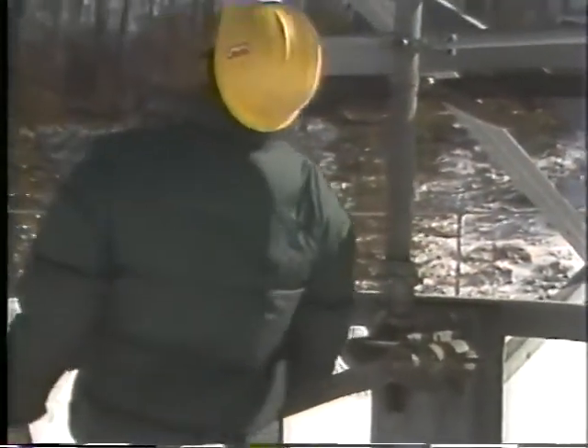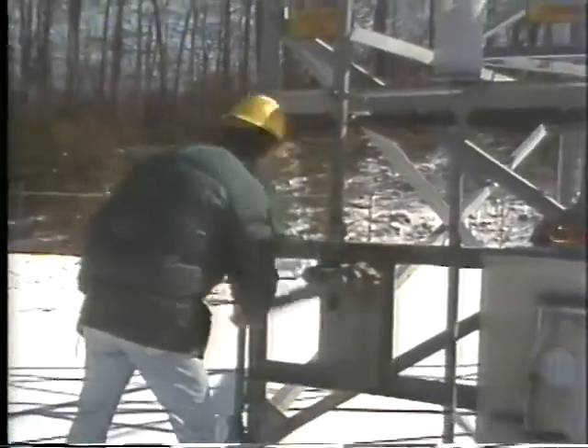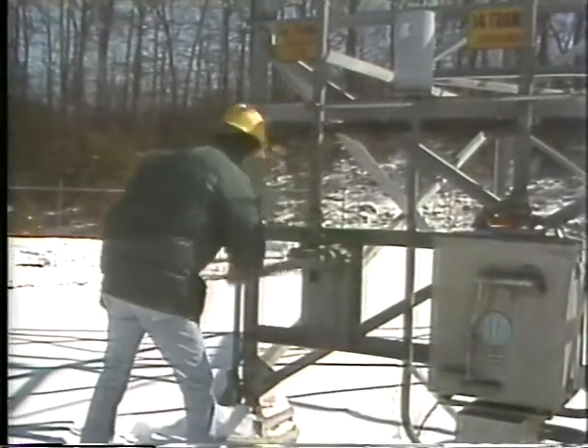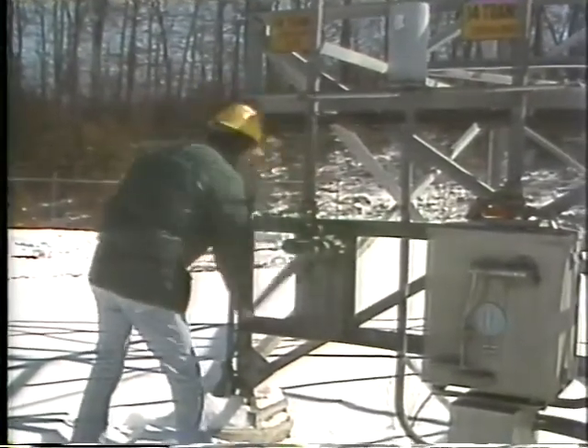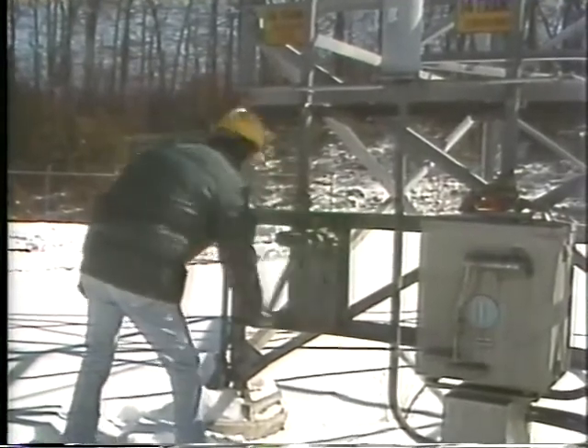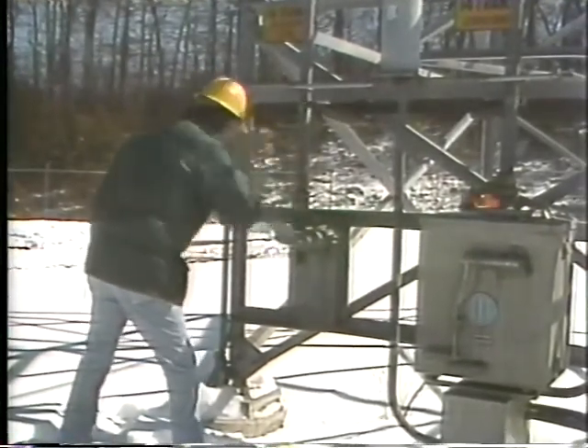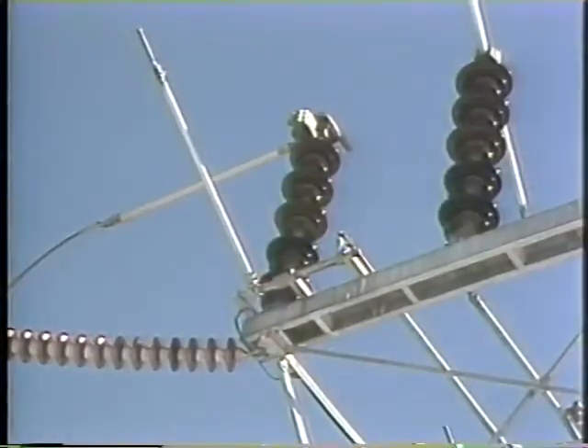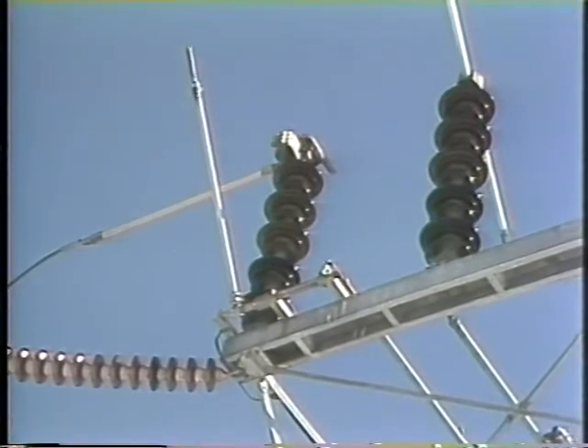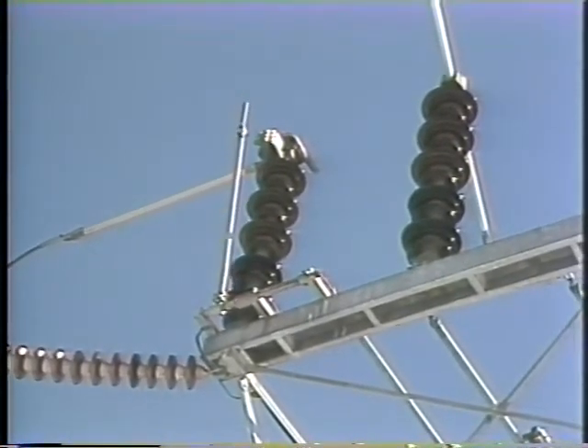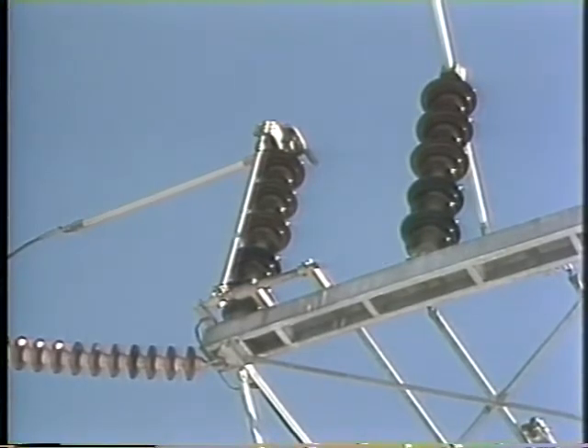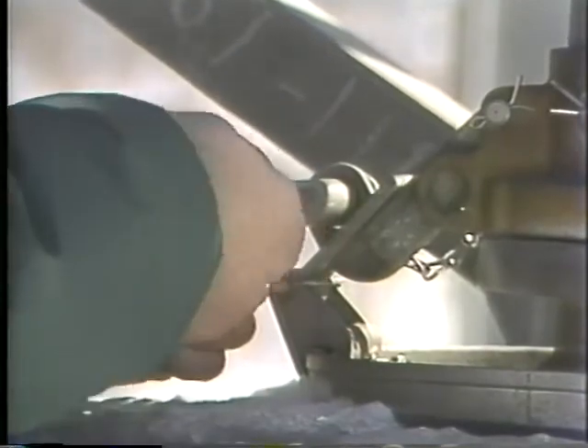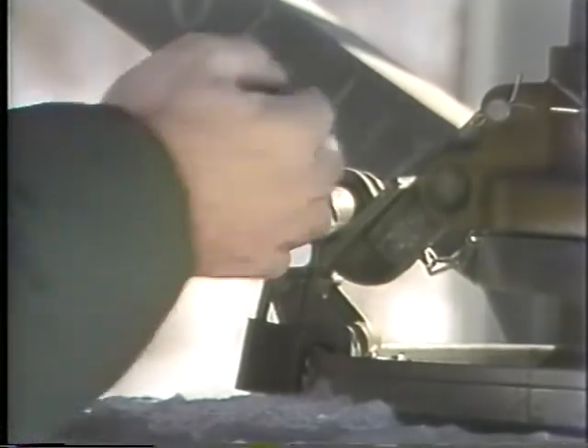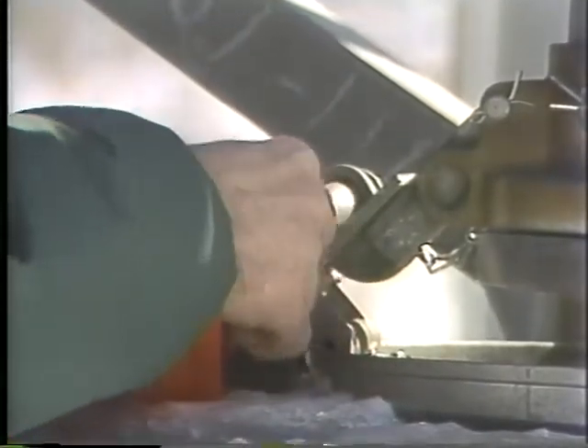Before starting work on the primary, he has one last precaution to take. He has to ground the primary. The ground's closed by this manually operated switch. Turning the crank closes the grounds on all three phases. Once they're closed, any induced voltage on the primary is discharged into the earth. If he had to work on the secondary side as well, he'd have to attach portable grounds over there. To make sure the primary stays grounded, he locks the switch in the closed position and tags it out so the ground won't be opened while he's working on the transformer.